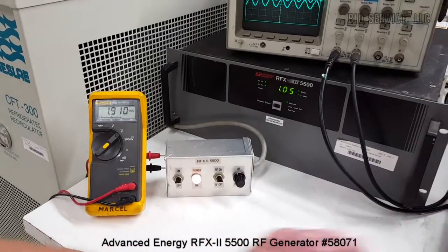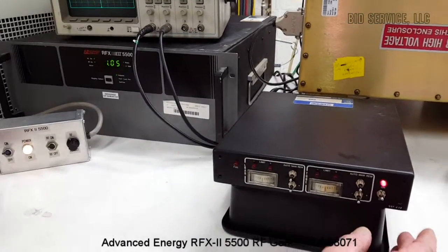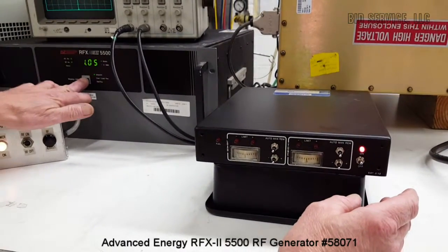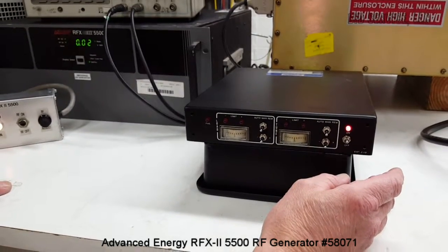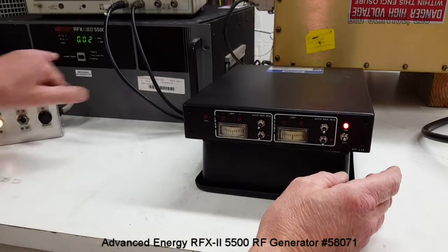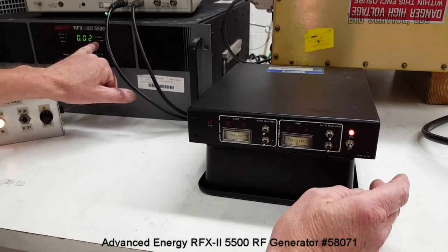This is the control for the matching network. If I switch to the display of reflected power, the reflected power is very low, which is what we're trying to accomplish when we operate.